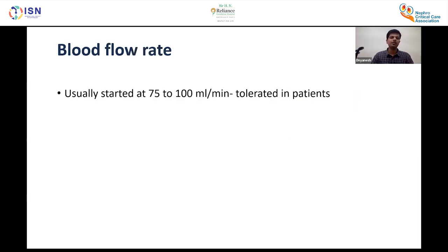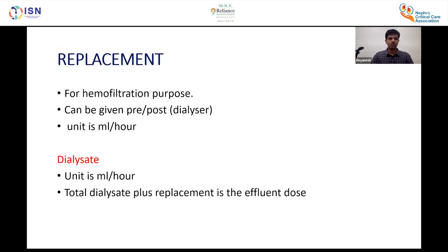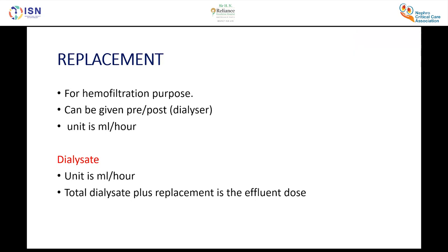Blood flow rate is the rate at which blood is withdrawn from the patient, usually started at 75–100 ml/minute. It depends on patient tolerance, ongoing inotropes, and volume status. Replacement fluid for hemofiltration can be given pre- or post-dialyzer, measured in ml/hour. The combination of the dialysate plus replacement fluid removed from the patient is known as the effluent dose.